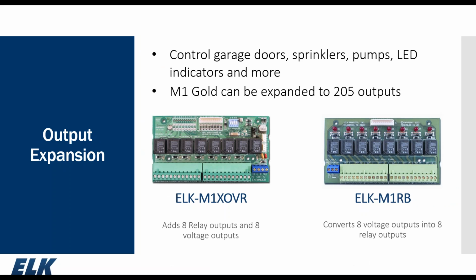For greater expansion, with the M1, you can have up to 208 total outputs. We offer the M1 XOVR. This is our 8 relay and 8 low voltage output board, connects to the data bus. So it can be remotely located. If it makes more sense to have the XOVR in a mechanical room or where the solenoids for the sprinkler system are located, you can certainly do so. By taking the M1RB and connecting it to the XOVR, you now convert the low voltage outputs into actual Form C relays. So with the addition of these 2 boards here, the XOVR and the M1RB, you now have 16 physical Form C relays connected to the data bus.